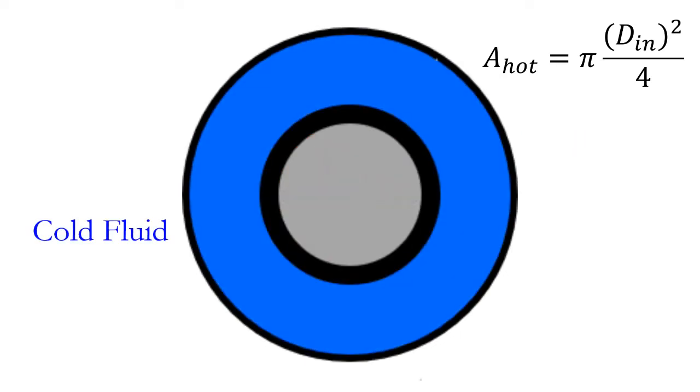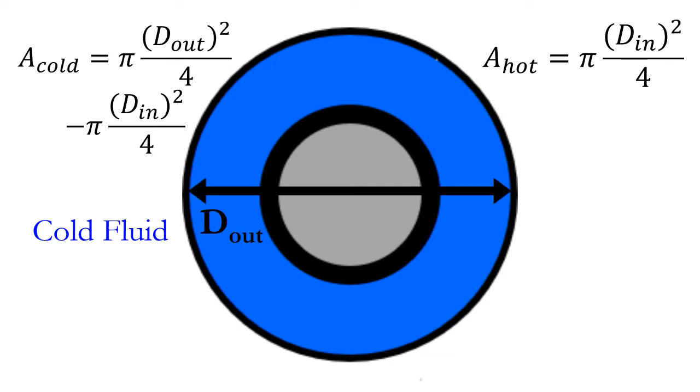The area for cold fluid flow is the cross-sectional area of the annular space in the outer pipe. To determine this area, we must subtract the circular cross-sectional area of the inner pipe from the circular cross-sectional area of the outer pipe, using the inner diameter from the large pipe and the outside diameter of the small pipe in our formula. Remember that the inner diameter of the annulus is different than the inner diameter of the middle pipe.